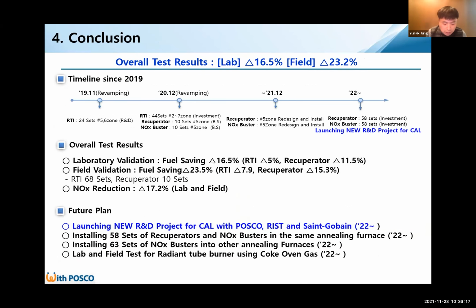In conclusion, the lab test result is 16.5% and the field test is 23.2% in terms of energy saving. Especially, RTI's 68 sets are installed in all zones except zones 1 and 8, and they run successfully without any troubles. And we have confidence in the energy saving effect of the newly designed recuperator.